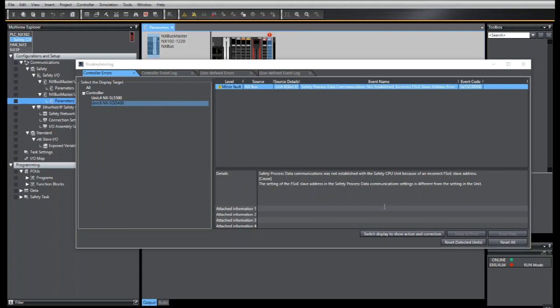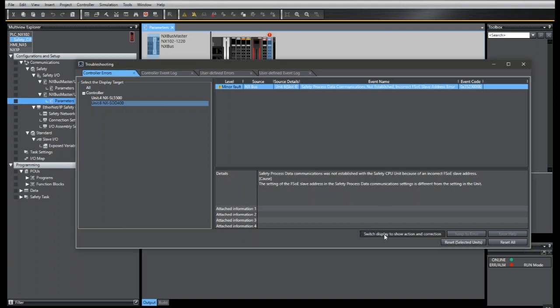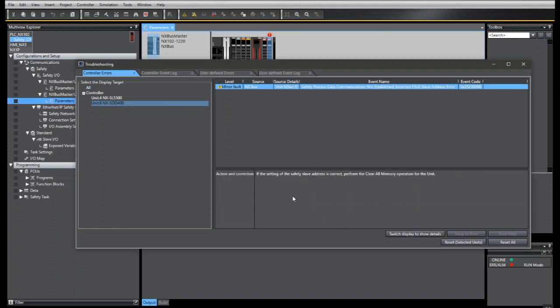As you see in the troubleshooter here, we have an incorrect FSOE slave address error. If we switch to display to show action and correction, you will see here that it wants us to clear all the memory on the unit.